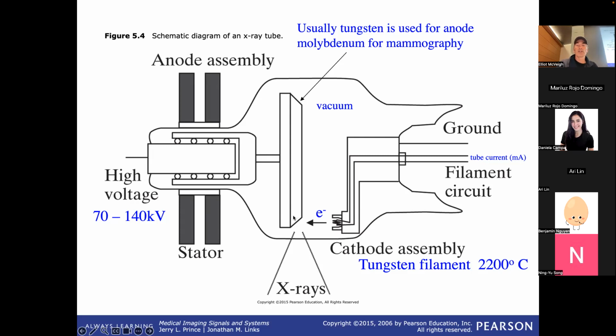There's usually a rectangle on this target, and the target is spinning. And so the continuous impact of electrons on that substance heats it up a lot. But because it's spinning, it averages that heat around, and the heat is usually drawn off via conduction.